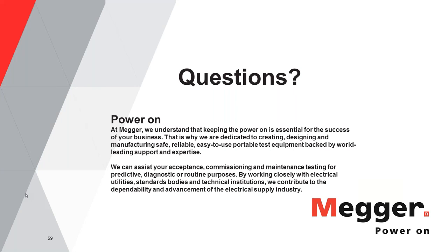So running a primary injection test, even though the current is high, is very safe. It won't cause any reduction in the life of the operation of the circuit breaker. And that's the reason why this test is recommended in the IEEE standards, in the NETA standard, in the NMAC standard, which most of the nuclear regulating agencies follow. So this is a very common test, and you would not take any life out of the breaker if you do this test.